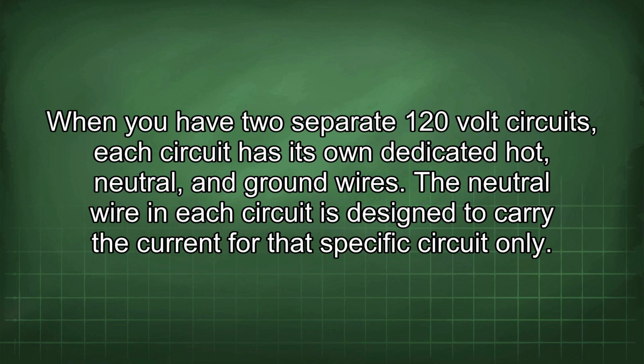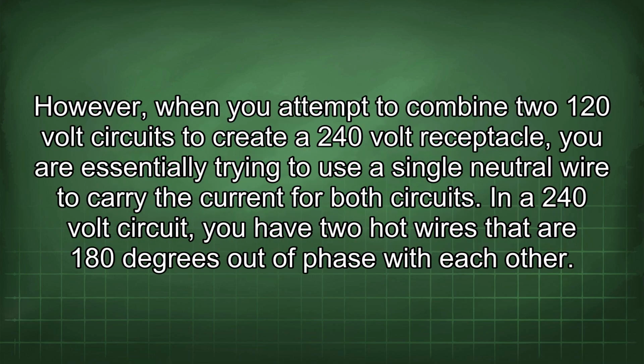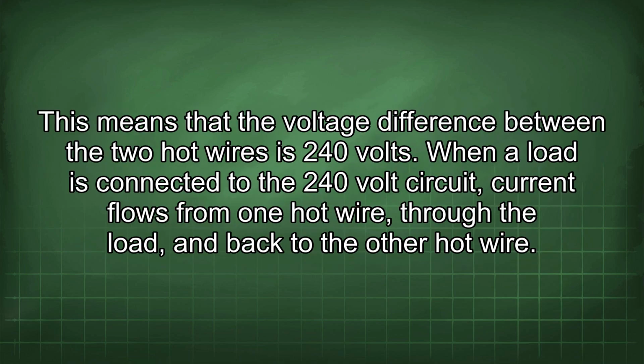When you have two separate 120-volt circuits, each circuit has its own dedicated hot, neutral, and ground wires. The neutral wire in each circuit is designed to carry the current for that specific circuit only. However, when you attempt to combine two 120-volt circuits to create a 240-volt receptacle, you are essentially trying to use a single neutral wire to carry the current for both circuits. In a 240-volt circuit, you have two hot wires that are 180 degrees out of phase with each other. This means that the voltage difference between the two hot wires is 240 volts. When a load is connected to the 240-volt circuit, current flows from one hot wire through the load and back to the other hot wire.